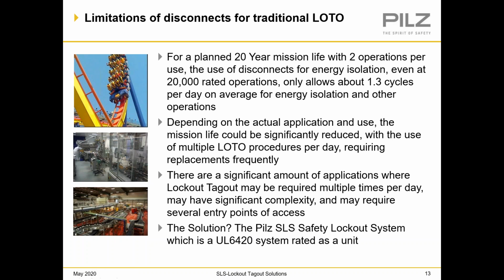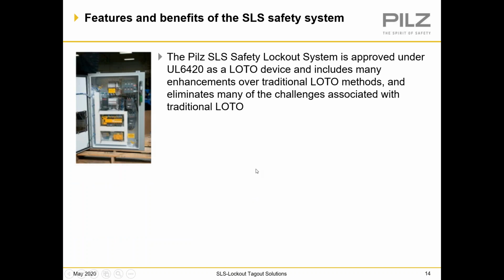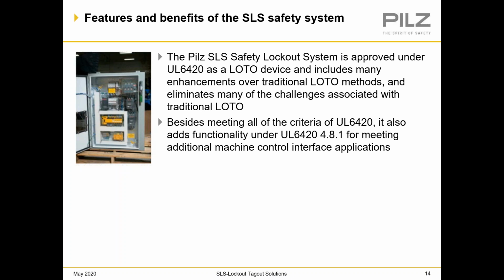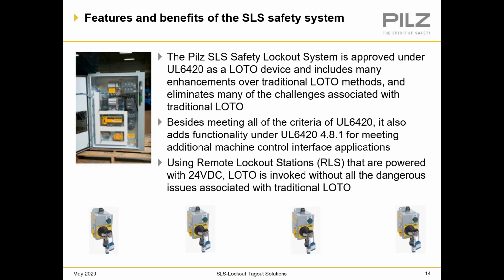So the solution is the Pilz SLS safety lockout system, again, which is UL 6420 rated as a unit. The SLS system is approved under the 6420 as a lockout device and includes many enhancements over traditional lockout methods and eliminates many of the challenges associated with traditional lockout. Besides meeting all the criteria of the UL 6420, it also adds functionality under 6420 4.8.1 for meeting additional machine control interface applications, and I'll show you what that means in a little bit here.